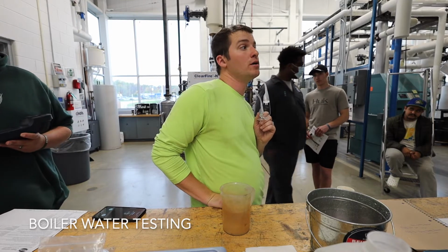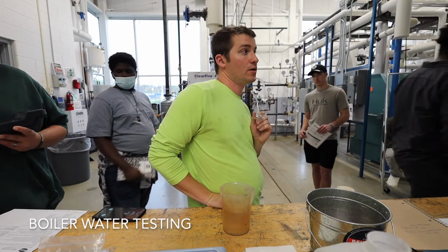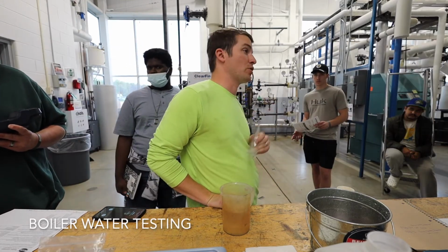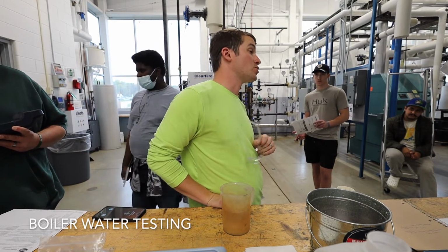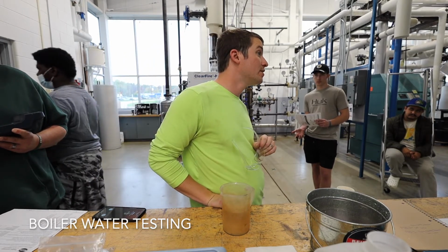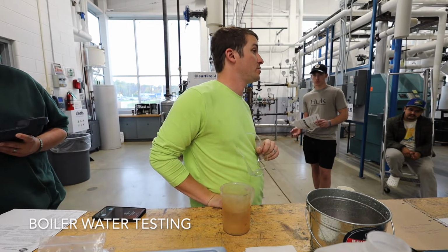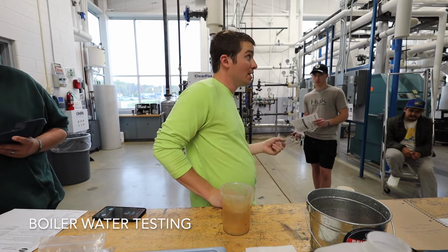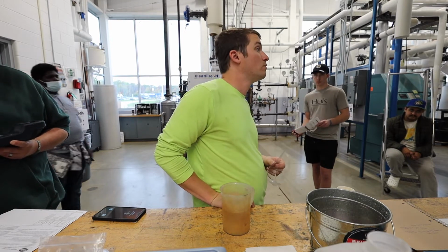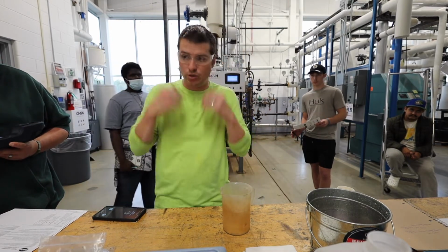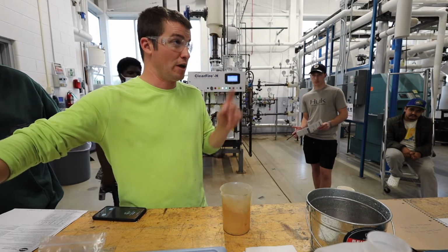You could have 1 part per million of OH alkalinity. Well, I know that for the product to work, I need to have like 150 minimum. So it's more important for me to know the alkalinity, and then know that if I have enough OH, my pH is going to be where it needs to be. Versus if I know my pH is where it is, but I might not have enough OH. So that's why I would tell you that this is more important in a boiler.